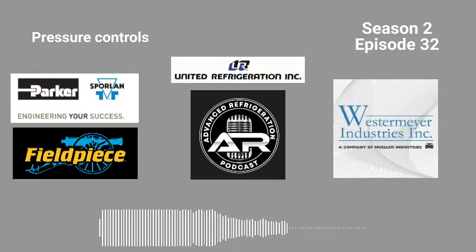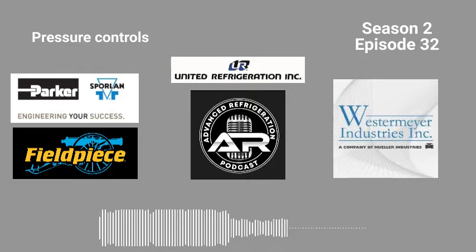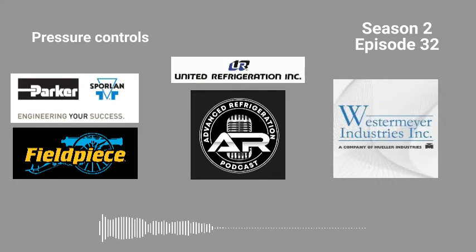If the rack is favoring the biggest compressor, make the biggest compressor run first and stage the others later. Look at the EMS trends — it'll give you a good idea of how to stage these, which compressors the rack favors, which ones run better. Every single rack is going to be different. This is kind of a pain — I wouldn't do this on every single PM. Probably once a year, checked in the wintertime when you're slower. Or when you take over an account, make sure it's set up, because you don't want a guy doing this in the middle of the night.